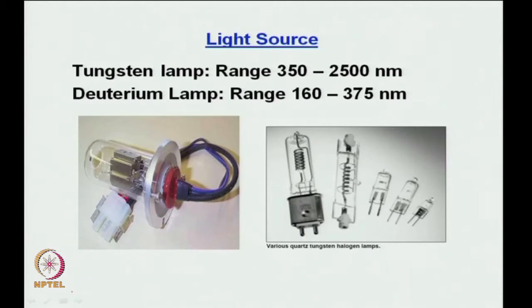So, this is how a deuterium lamp looks. This is typically how it would look. Now, since I have given you the picture, you can take your laptop out there, in front of the computer, and compare it with the lamp you have inside. It should match. If it does not match, come back and let me know, okay. Then I will know something new. Anyway, on the right side is your tungsten halogen lamp.